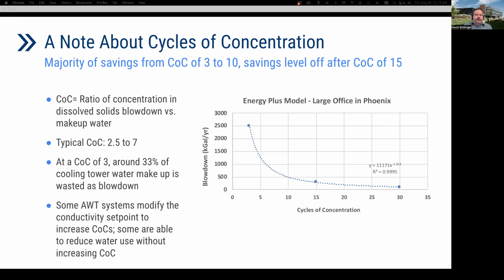So for those involved with cooling tower operation, likely familiar with cycles of concentration, or COC for short, it's the most common metric used to represent water efficiency in cooling towers. It describes the mass relationship between the amount of makeup water and the amount of blowdown discharge to the drain. So high COCs are directly related to low levels of water loss from your system. GSA requires a COC value greater than 2. So at a COC of 3, around 33% of cooling tower water makeup is wasted as blowdown. So some of the AWT systems modify the conductivity set point to increase the COCs. Some are able to reduce water use without increasing the COC. Again, this is just a metric.